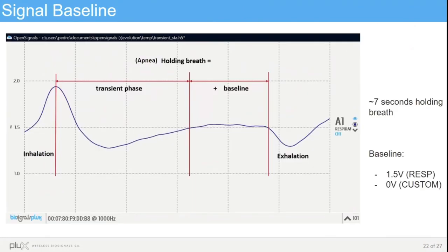That's because the sensor measures displacement. When the ribcage is not moving, the cross-sectional area of the core of the coil is not moving, so all the measures stay the same. If all the measures stay the same, the frequency of the oscillation circuit will not change, and so the energy stored in that circuit will be dissipated, leading the signal to go to the baseline. Once the chest starts moving again, all the measures will vary, and so the signal will also change.